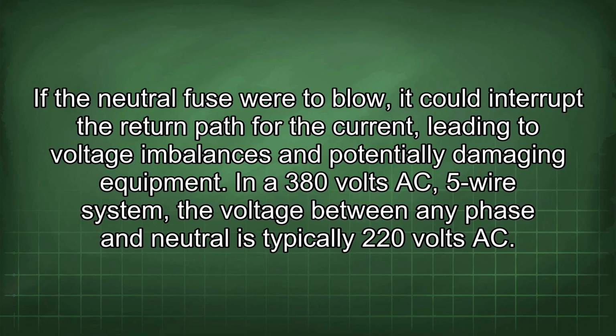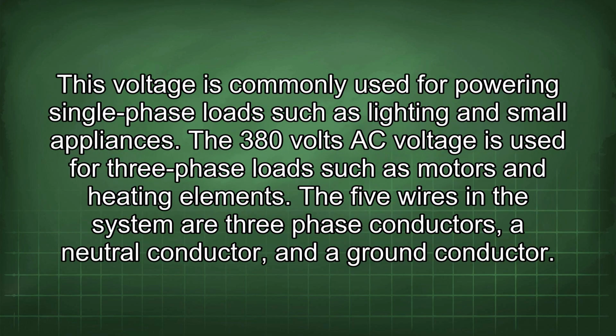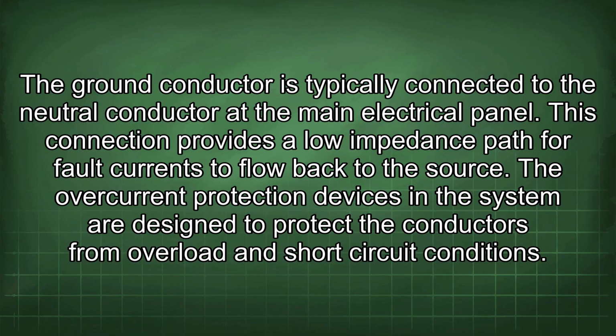and potentially damaging equipment. In a 380 volts AC 5-wire system, the voltage between any phase and neutral is typically 220 volts AC. This voltage is commonly used for powering single-phase loads such as lighting and small appliances. The 380 volts AC voltage is used for three-phase loads such as motors and heating elements. The 5 wires in the system are three phase conductors, a neutral conductor, and a ground conductor. The ground conductor is typically connected to the neutral conductor at the main electrical panel. This connection provides a low impedance path for fault currents to flow back to the source.